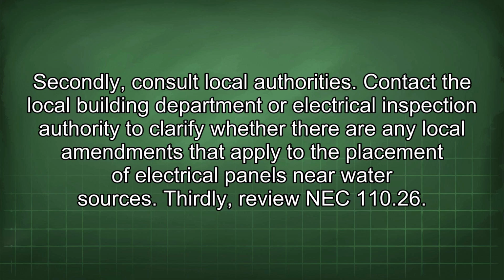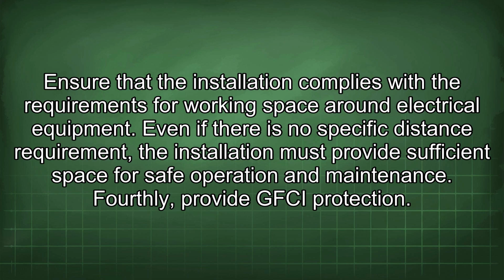Thirdly, review NEC 110.26. Ensure that the installation complies with the requirements for working space around electrical equipment. Even if there is no specific distance requirement, the installation must provide sufficient space for safe operation and maintenance. Fourthly, provide GFCI protection.